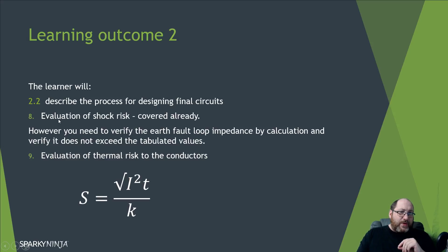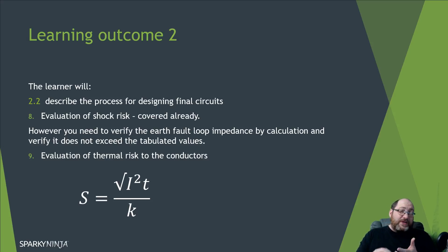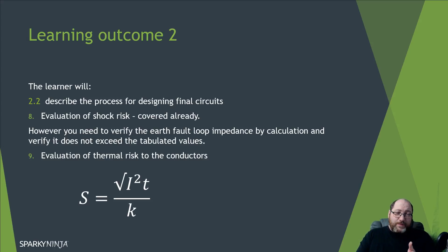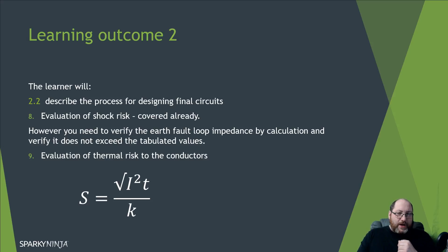Once we've done that, we evaluate the shock risk and the thermal risk — making sure that the conductors we've selected can carry the load for the duration they'll carry it, and that the protective conductor selected is also suitable for the fault current that will flow. It's basically just checking. Once we have a cable selected, we can also verify the earth fault loop impedance.